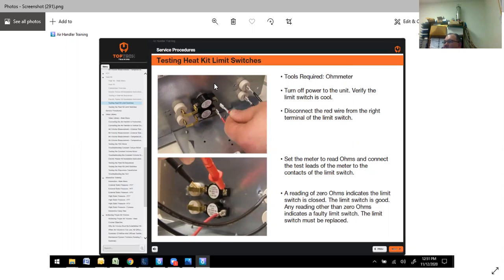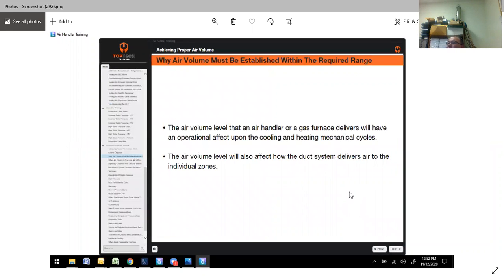Now, if you're going to check the heat kit limit switch, basically you're going to check at the bottom here. Set it on ohms reading with no power on, and then you're going to check from one side of the limit to the other side of the limit. A reading of 0 ohms indicates that the limit switch is closed, which is what you're wanting if the limit switch is good. If that limit switch is open, that switch is bad. So you've got some airflow issues to work on to figure out why you're overheating. Dirty filters, closed off vents, you know, the list goes on.